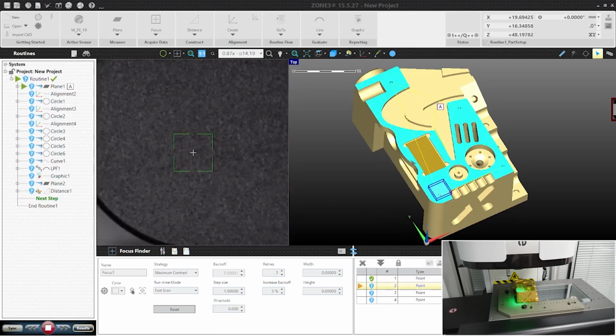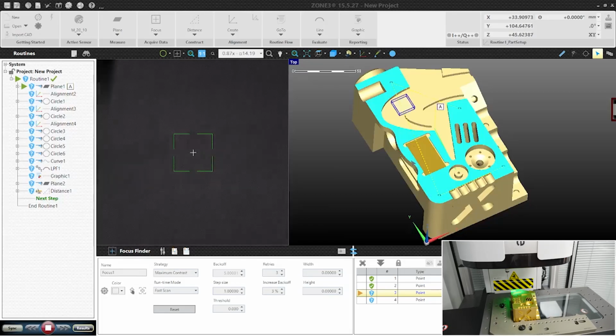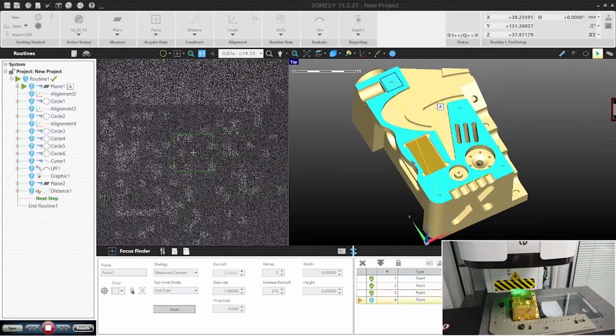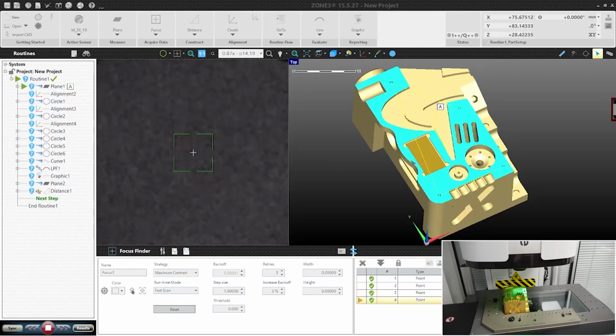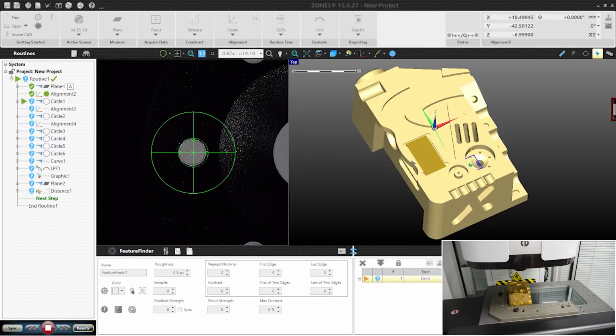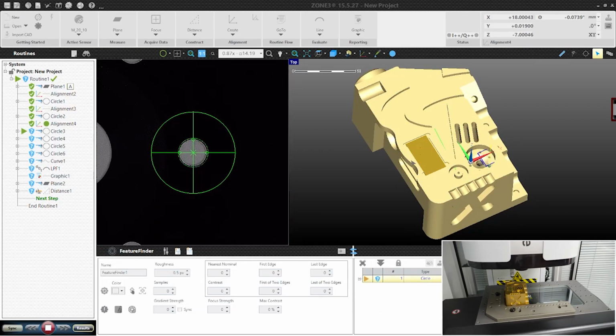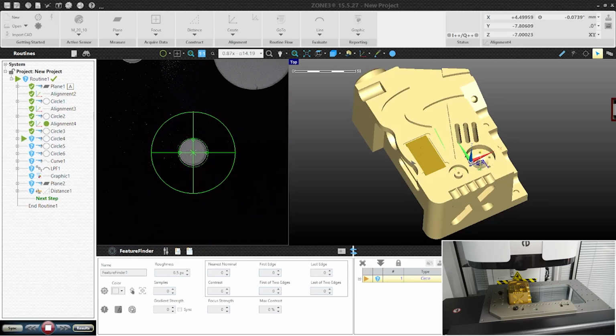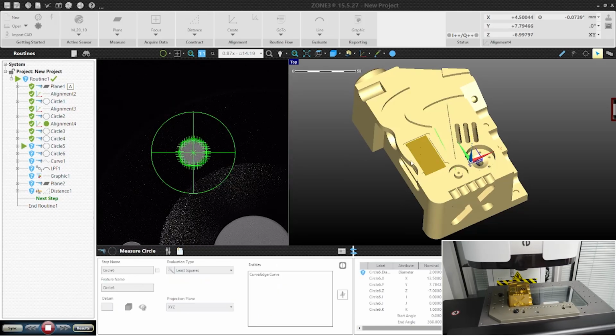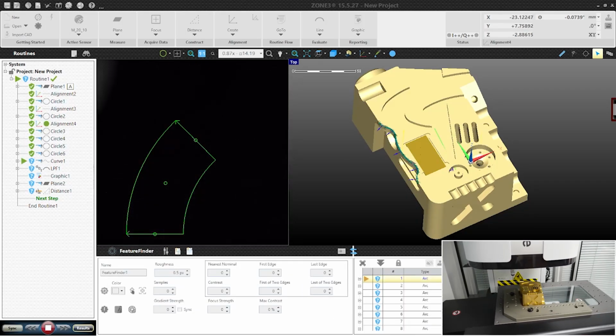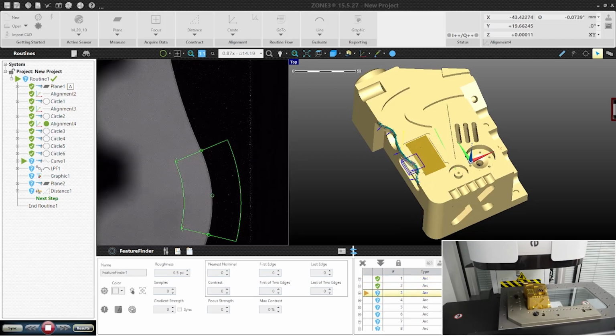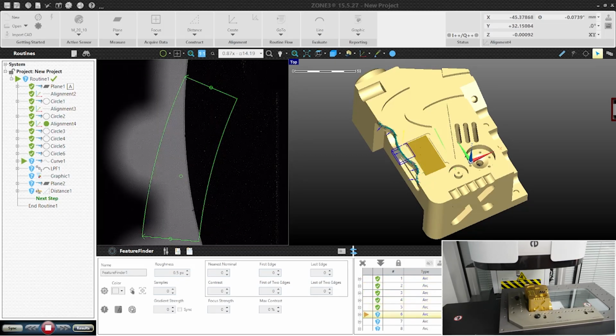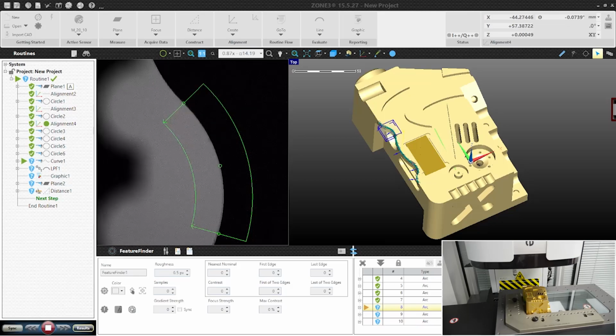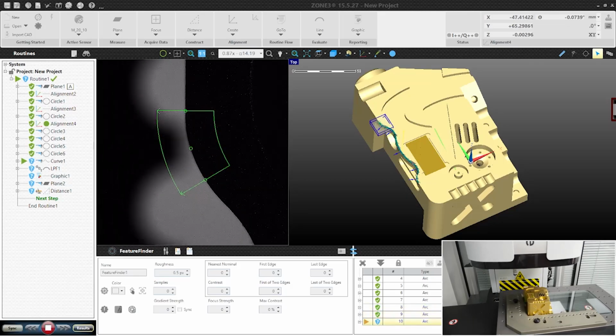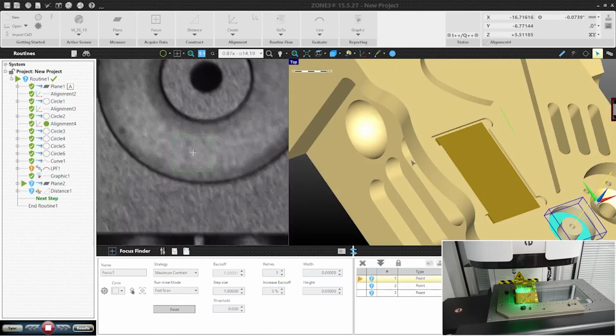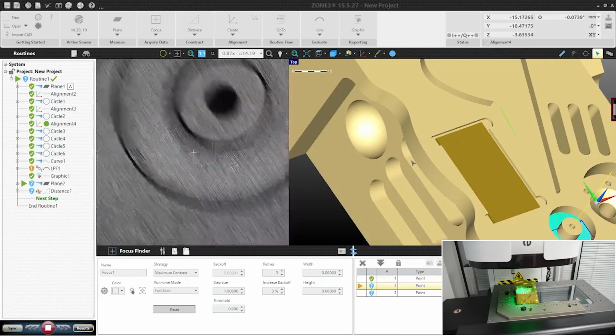So we're measuring a plane on the top face using autofocus with the optics. And that is setting alignment on the top face. We're measuring the two holes to set an origin and axis. This is where we apply to similar to auto program the other holes. And now it's measuring the freeform curve on the left hand side of the part. We're going to compare that to the CAD model and then give you a graphical report. So swapping back to the autofocus to measure the depth.